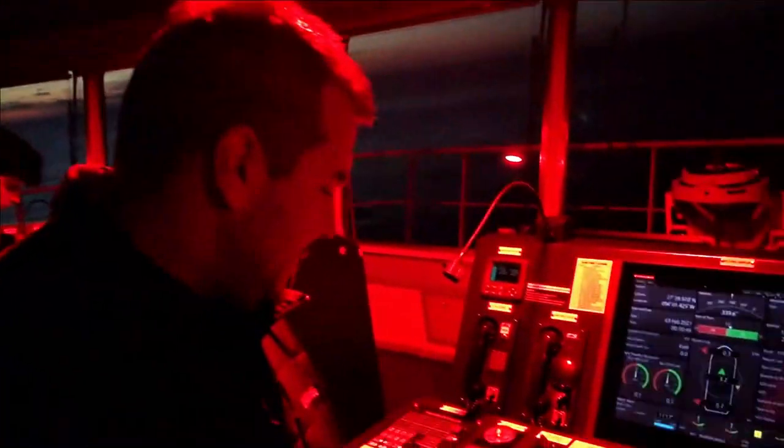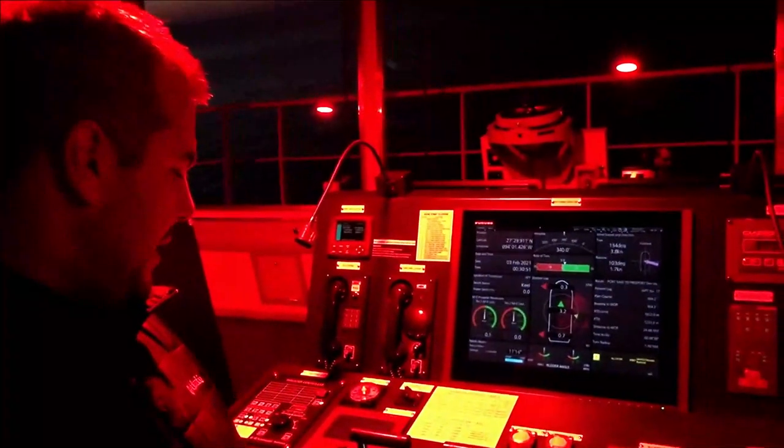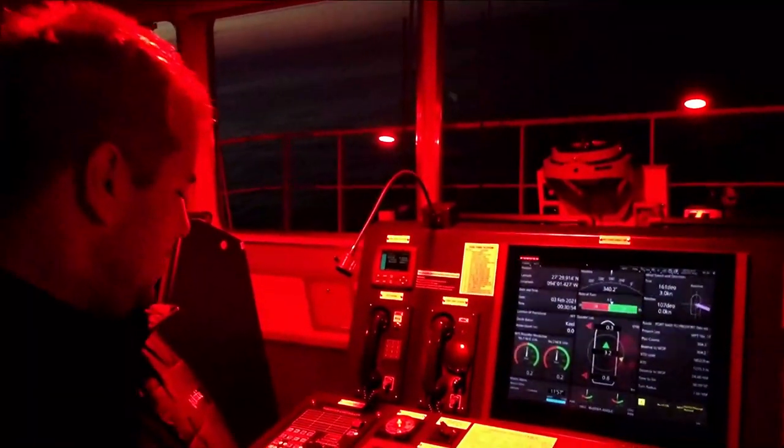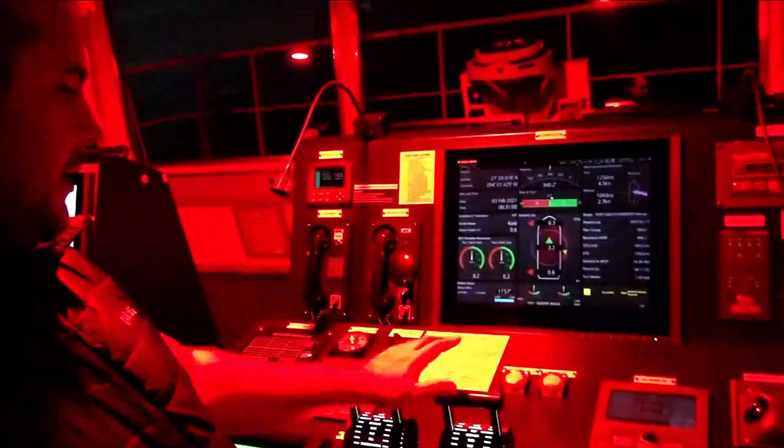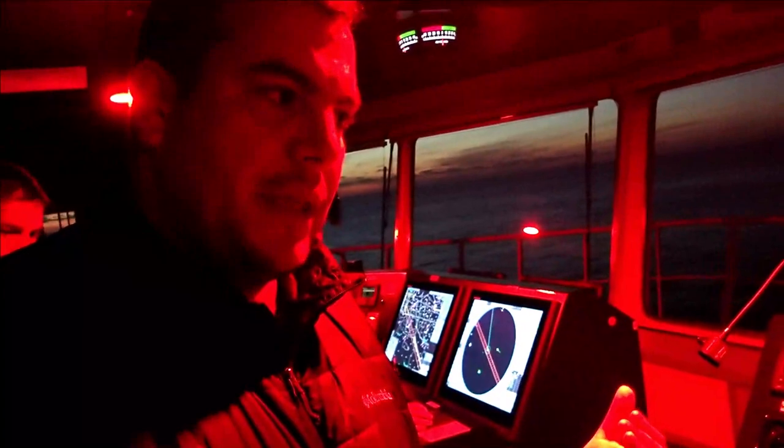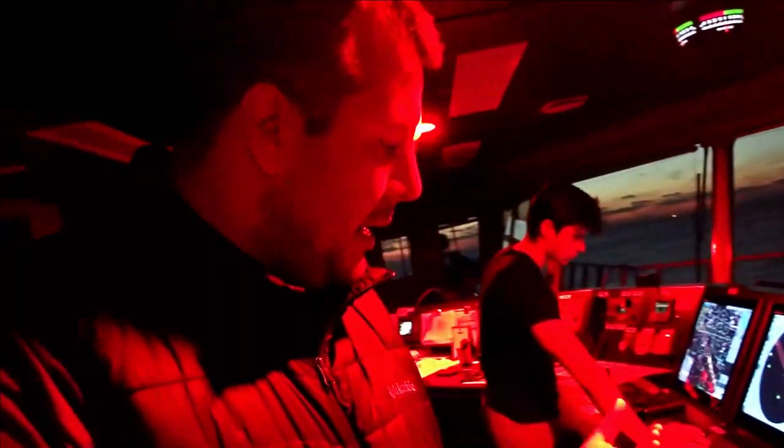I'm back in the bridge, and it's time to take the controls from inside here. So I have to go and press the bridge, and the bridge is in command. So these controls are ready. We go now to perform the steering gear test with the third engineer, who's down in the steering gear room, and the electrician, who is also with him. And yeah, we're going to do those tests and establish that everything's working out right. Guys, please check that all indications are operational, and let me know if there's anything we need to check. So, all right. Thank you.